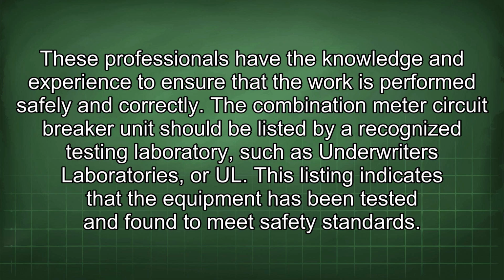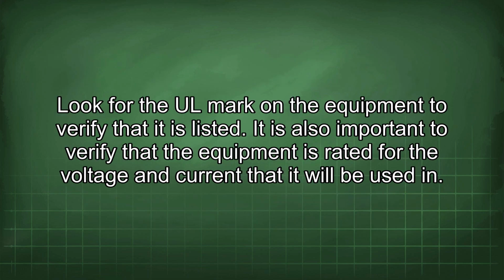The combination meter circuit breaker unit should be listed by a recognized testing laboratory such as Underwriters Laboratories, or UL. This listing indicates that the equipment has been tested and found to meet safety standards. Look for the UL mark on the equipment to verify that it is listed.